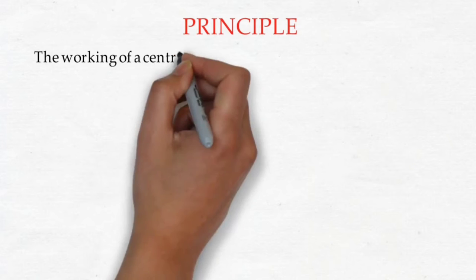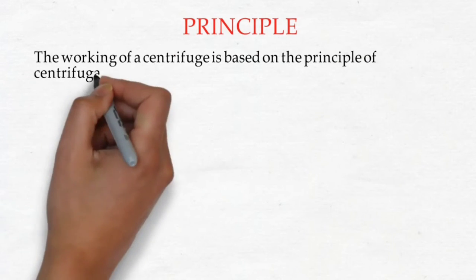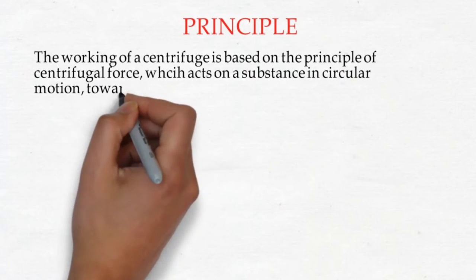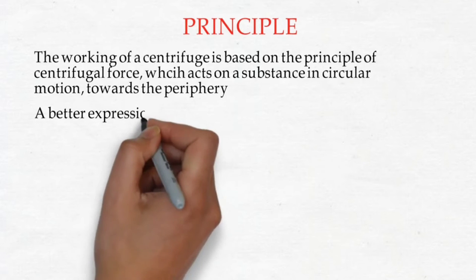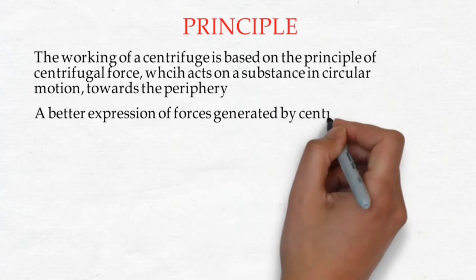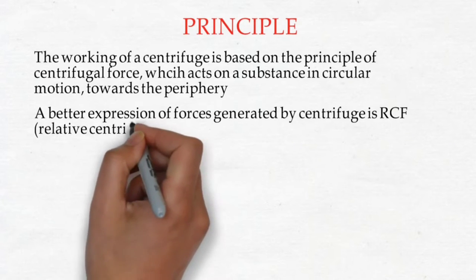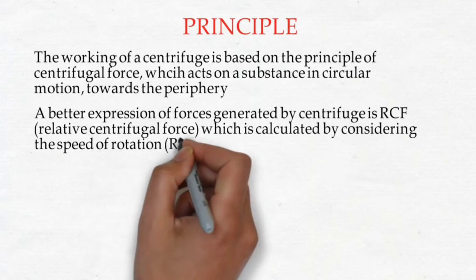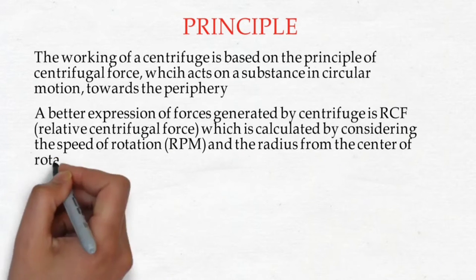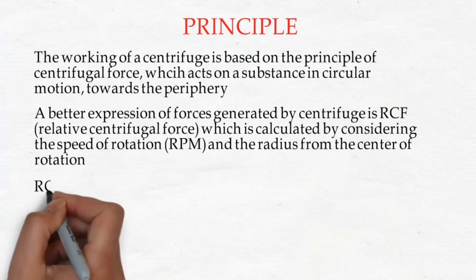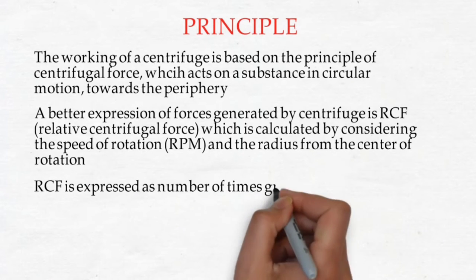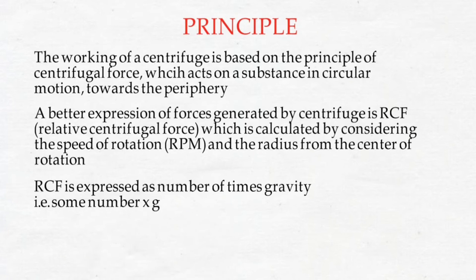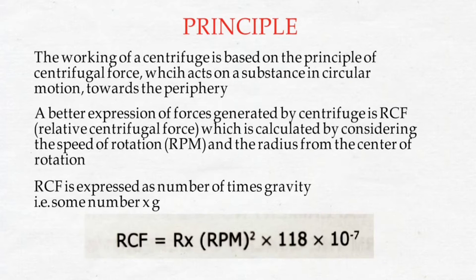The working of a centrifuge is based on the principle of centrifugal force, which acts on a substance in circular motion towards the periphery. A better expression of forces generated by a centrifuge is RCF — Relative Centrifugal Force — calculated by considering the speed of rotation in RPM and the radius from the center of rotation. RCF is expressed as a number of times gravity, and the formula is: RCF = radius × RPM² × 118 × 10⁻⁷.